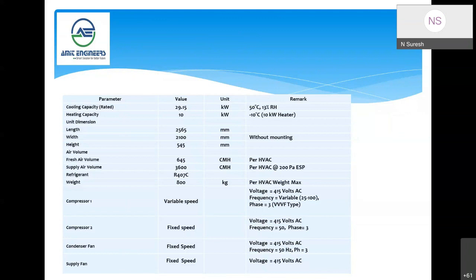And the unit dimension we have given is 2.5 by 2.1 by 0.5 meters without mounting. And these are all the air volume which the unit will deliver at this much static. And the refrigerant we are using is R407C. From a maintenance perspective, to tell briefly about this refrigerant, this is basically a blend of 3 gases. So for handling, or anytime charging or removing, there are good practices mentioned. We have to follow that so that the system will not have any problem in operation.